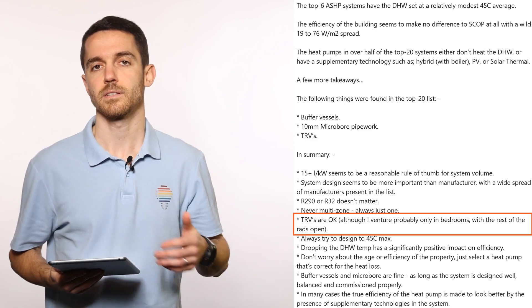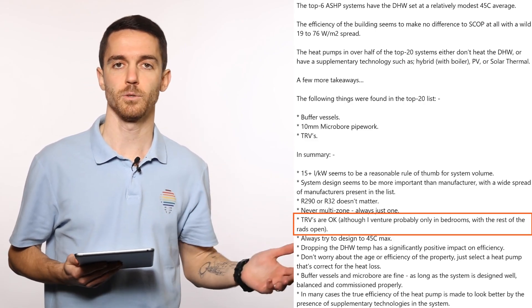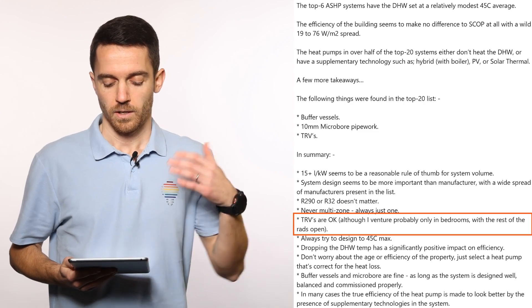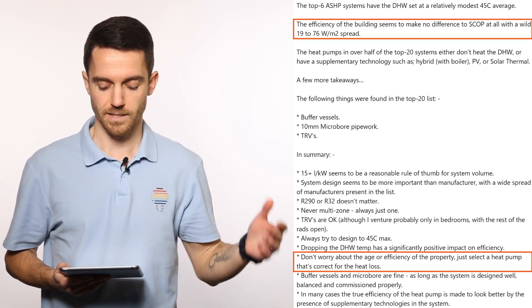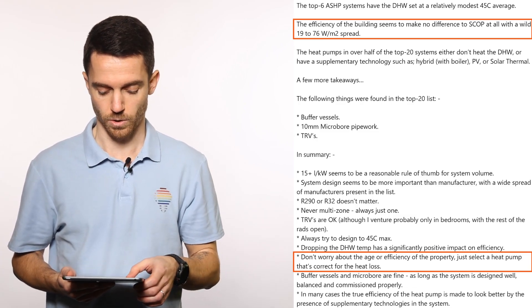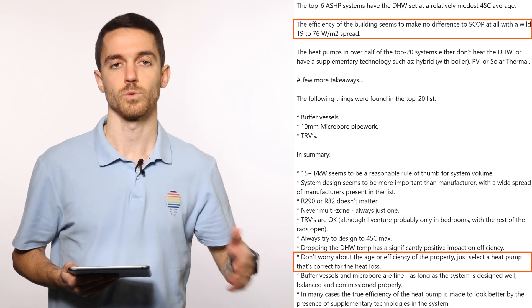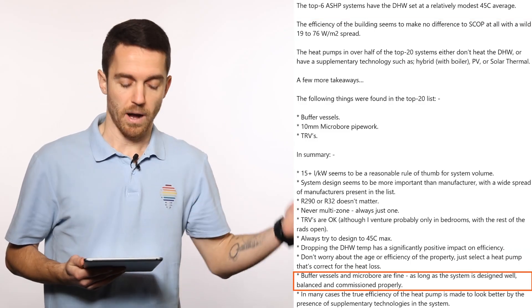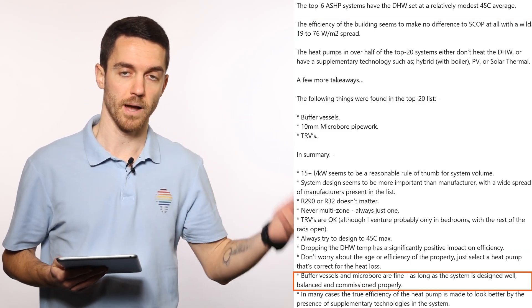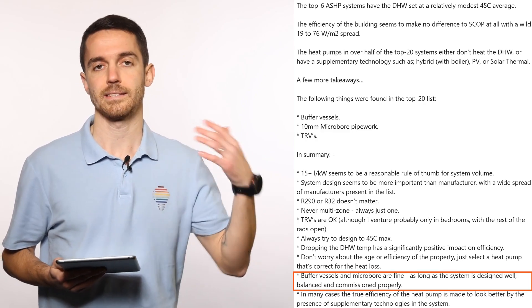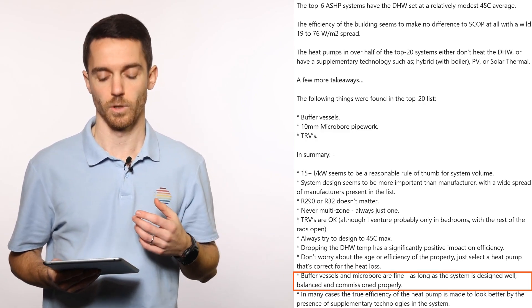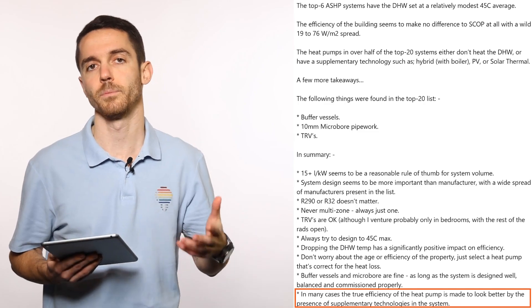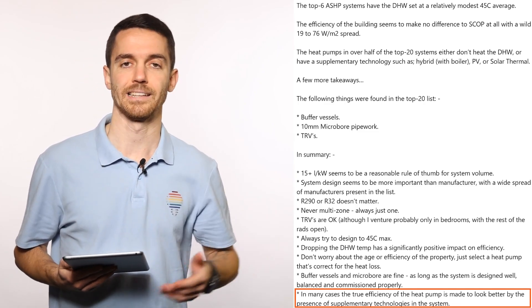Thermostatic radiator valves and zone regulation are probably good in bedrooms and small zones, but open volume in all other zones is the approach to go. 45 degrees maximum flow temperature — it doesn't matter if your property is old or new. You can find systems from 19 to 76 watts per square meter on Open Energy Monitor. Buffer vessels in combination with microbore — as long as the system is designed and balanced well, efficiency will be good. Top performing units are usually without domestic hot water, because DHW requires slightly higher flow temperature.